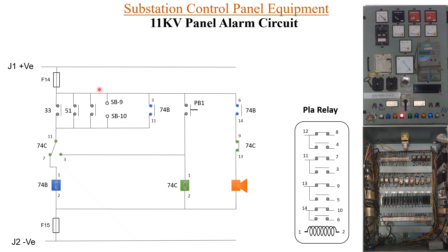Now let us see the animation for this alarm circuit. The relay will first get operated, due to which one of the contacts will be closed. When the relay is operated, you can see one contact will be closed — contact 51. Because of this, the coil 74B will be energized. And once this coil is energized, its both contacts will be operated. As the coil is energized, the self-latching contact has closed so it will continue to be energized.